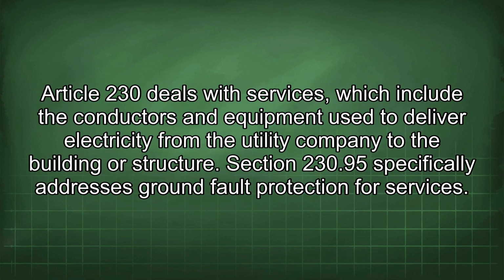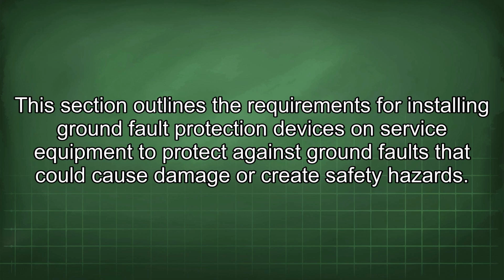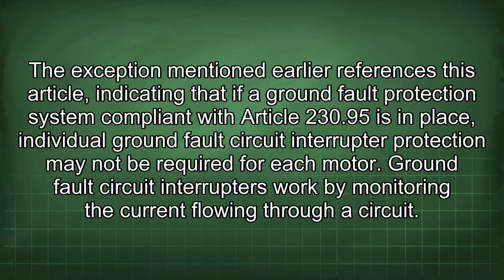Article 230 deals with services, which include the conductors and equipment used to deliver electricity from the utility company to the building or structure. Section 230.95 specifically addresses ground fault protection for services. This section outlines the requirements for installing ground fault protection devices on service equipment to protect against ground faults that could cause damage or create safety hazards. The exception mentioned earlier references this article, indicating that if a ground fault protection system compliant with Article 230.95 is in place, individual ground fault circuit interrupter protection may not be required for each motor.